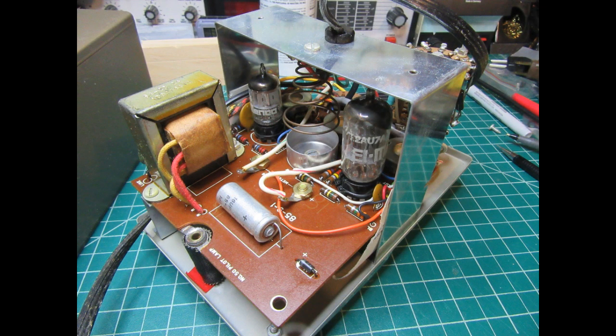Alright, here is the chassis looking at the top side of it. At the far left, we have a tubular device of black color, which goes from the circuit board right up to the front panel. In this instance, somebody's put a little piece of red tape in there, but that's where the pilot light goes, inside that black tube. And the tube is made out of a flexible, temperature-tolerant fabric material, which prevents light escaping and also just protects the bulb and will not get damaged by the heat of the bulb. And the pilot light is really just to tell you that the power is on, because otherwise you may not be able to tell. And it is not there to illuminate the meter, as some sources claim.